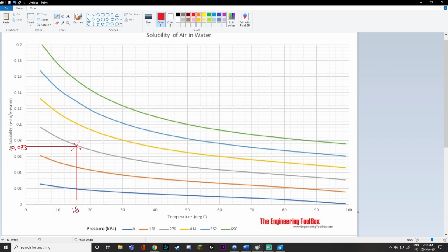Now, our water heater takes this water and it brings it to 60 degrees, which is going to be all the way over here. And it also brings it up to 600 kilopascals, brings us to around here. So we can see that we now actually have more room in our liquid, because now our liquid can store this much gas, but the amount of gas stays the same, because our water heater is not introducing more gas. So it takes it up to here, and now we are in the situation where we are asking our water heater for water and for it to come out of the faucet. And it is going to go from 600, we're going to do a straight line down, all the way to about 100 kilopascals. And we end up at this spot. And now if we track it all the way to the other side, we can see that we are at 0.02.